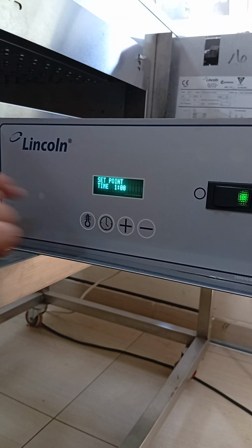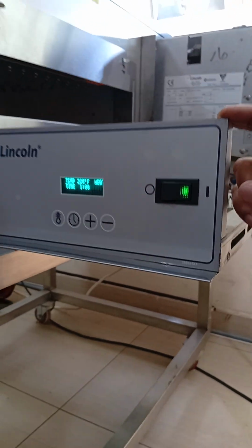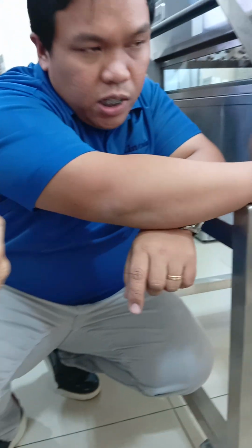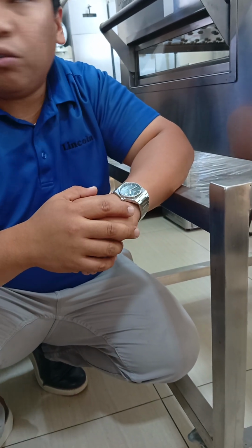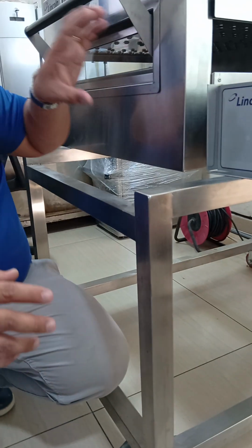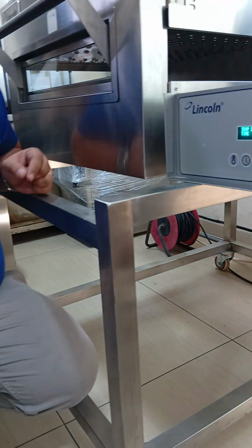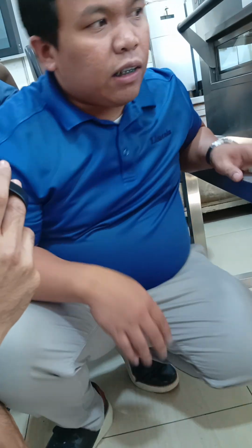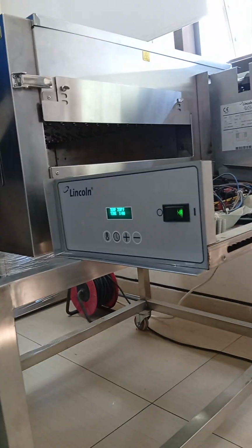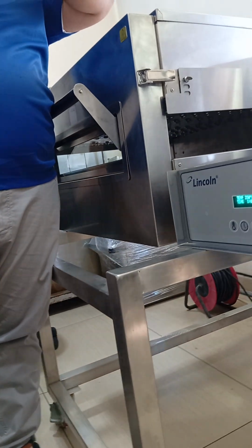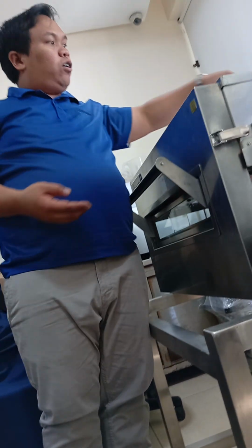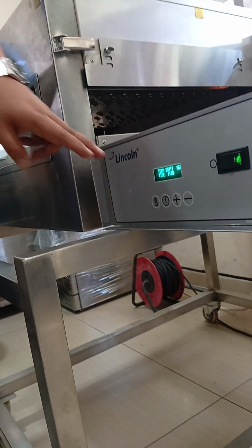Okay? So during the calibration, it is advisable to check the internal calibration by setting the temperature first to the maximum, or 260 Celsius, approximately around 500 Fahrenheit. Okay? And to check the internal temperature, you need to disconnect the chain to avoid moving your temperature probe. Since we have this impinger and we have only one temperature probe, we need to put the temperature probe sensor in the middle, inside. Okay? Then compare your temperature between the display and the actual.